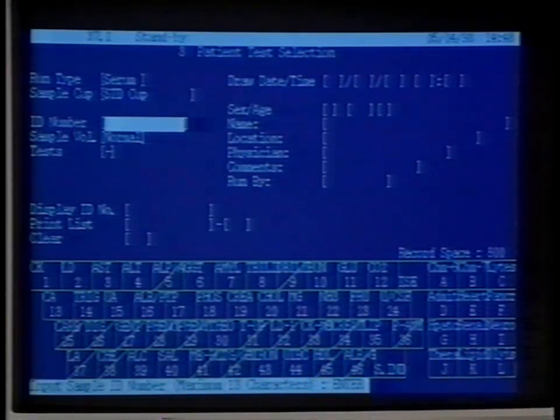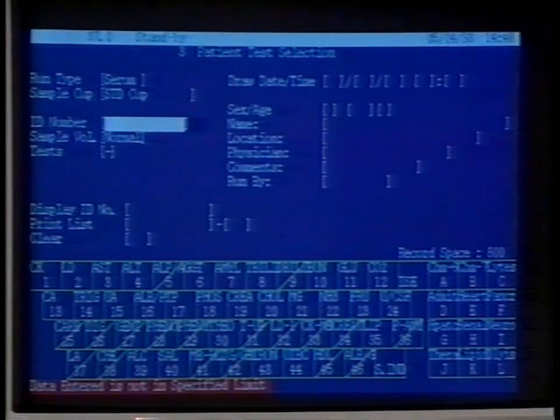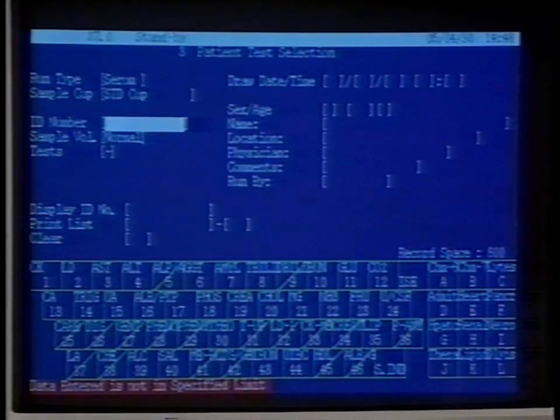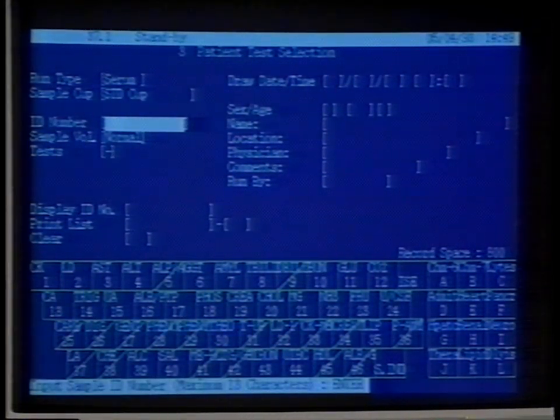The prompts display the allowable entries. A red error message will appear in the event an unacceptable entry is attempted. These two features, the prompts and error messages, make it very easy to learn how to operate the system. This part of the screen shows a graphic representation of the test selection keys on the keyboard. When a slash appears across a key, it indicates that the test is masked or turned off and can't be run, perhaps because the reagents haven't been added or were placed on the wrong disk. When the appropriate corrective action is taken, the analyzer will unmask the test.